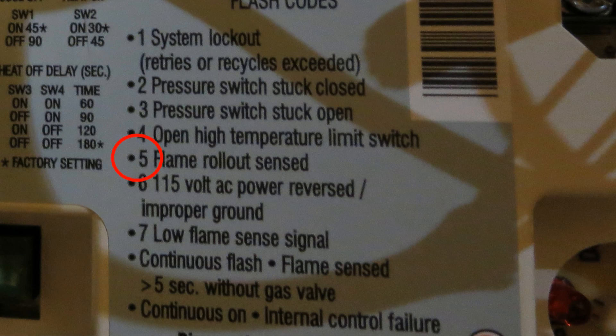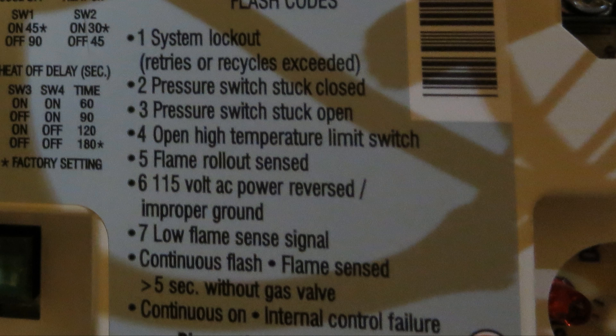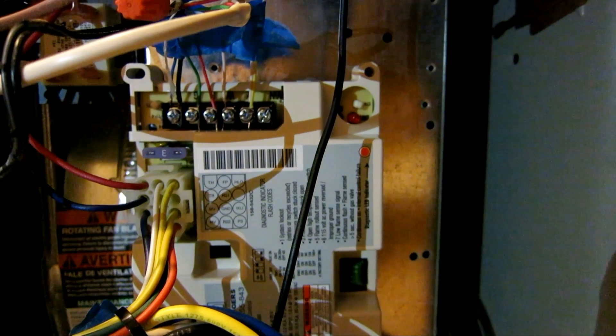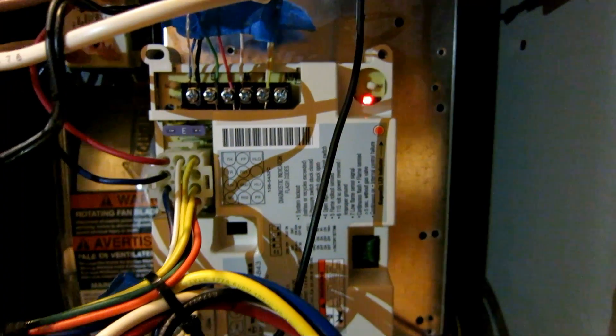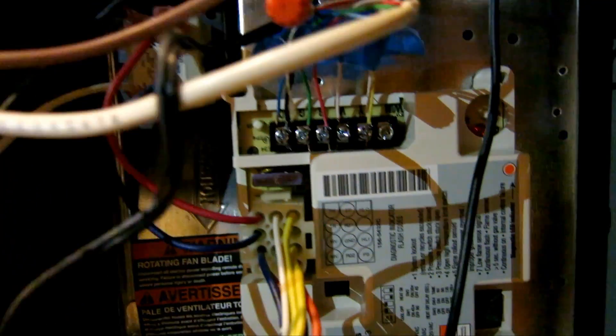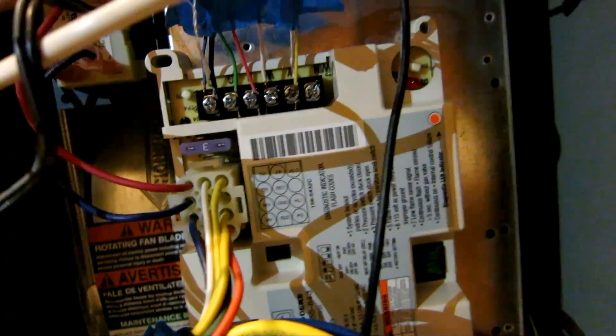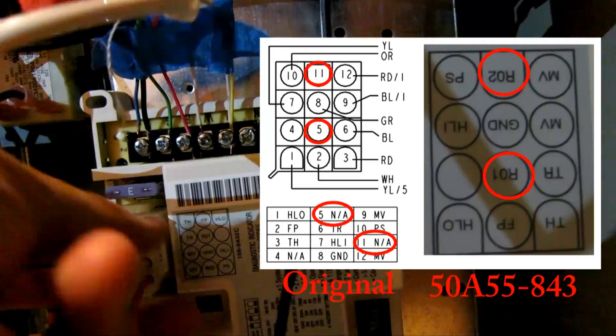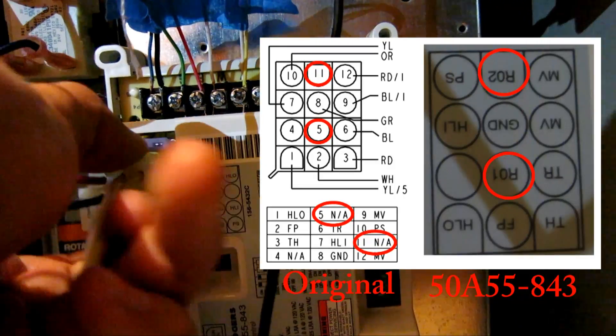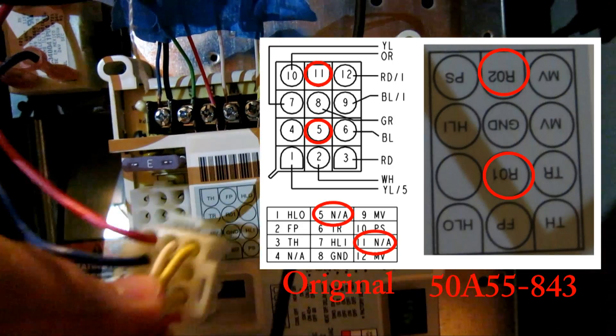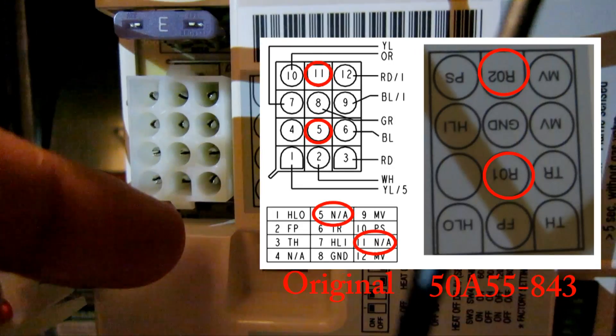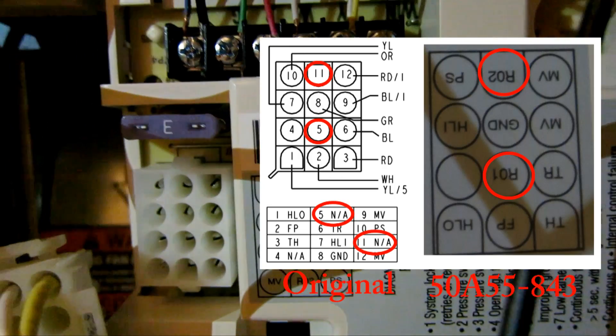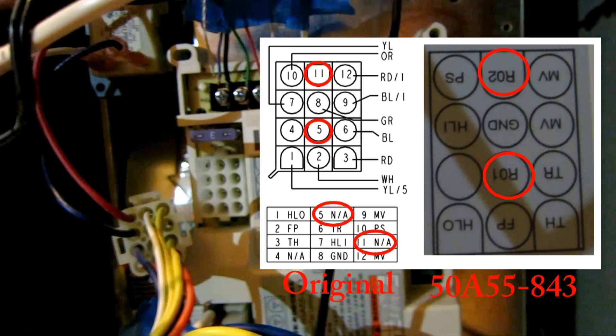And if you look at the fault chart right here, basically it means that the rollout switch is open, so there's an issue with the rollout switch. Let me stop that real quick. What's really going on is this furnace doesn't have a rollout switch. And if I compare this graphic right here with the original one...